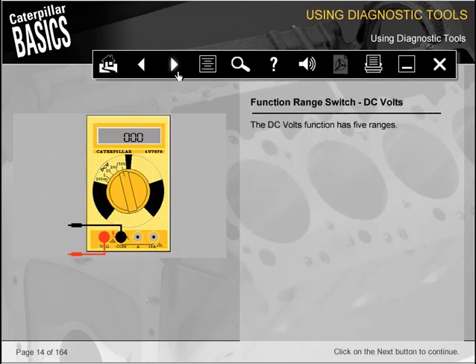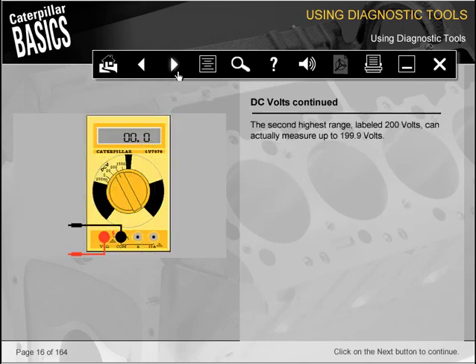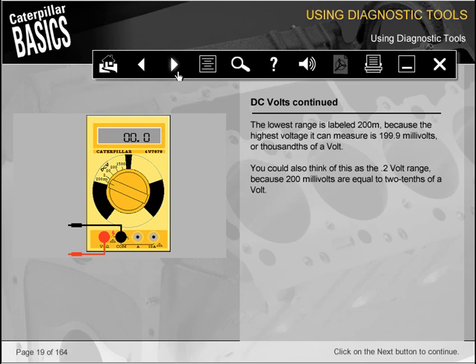The DC volts function has 5 ranges. The 1500 volt range is highest and can measure up to 1500 volts DC. The second highest range, labeled 200 volts, can actually measure up to 199.9 volts. Likewise, the 20 volt range can measure up to 19.99 volts. The 2 volt range can measure up to 1.999 volts. The lowest range is labeled 200M because the highest voltage it can measure is 199.9 millivolts, or thousandths of a volt. You could also think of this as the 0.2 volt range because 200 millivolts are equal to 2/10 of a volt.